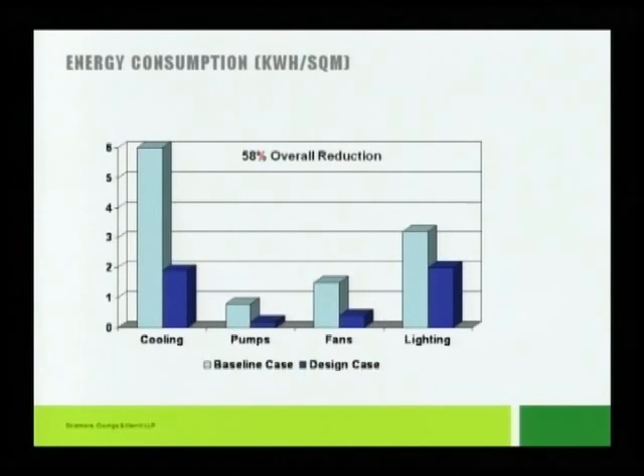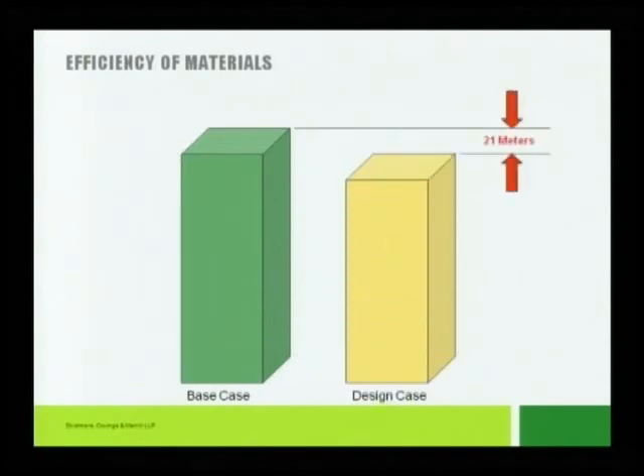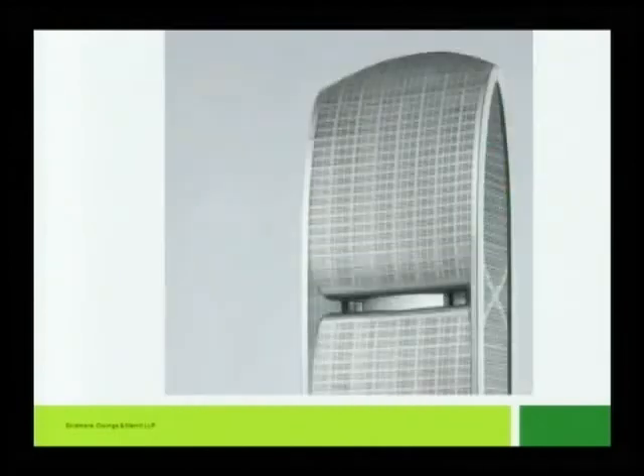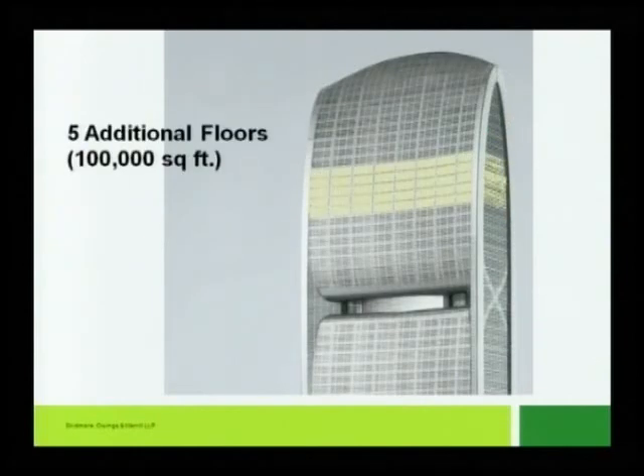This is a little graphic that shows you the reduced cooling, the reduced pumps and fans, because we've got very little in the way of air handling units, and the reduced lighting load. One big thing was this technique of using the radiant chilled ceiling and floor-fed ventilation allowed us to have a 3.9 floor-to-floor height, rather than a 4.2 or 4.5 typically in an all-air system. This saved 21 meters in the building, allowing us to get another 5 floors of free area, effectively, within the planning permission.